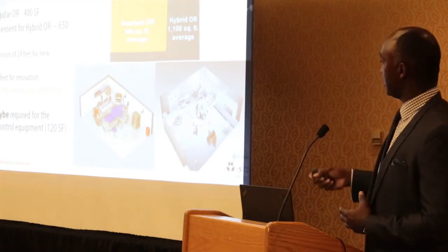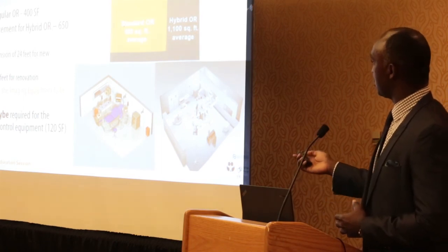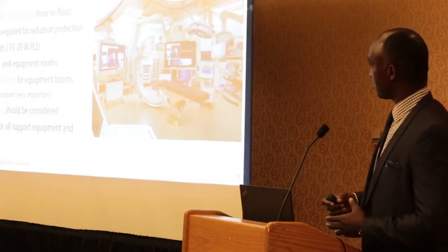A control room is required, which is another 120 square feet. So as designers, as facility managers, whenever you're trying to undertake these projects, there's a huge space requirement. And the minimum size of a hybrid OR that I've seen is 1,100 square feet. So that's the minimum size that you require, so you have to look out and make sure that you're not short on the size of your hybrid OR. And these are just some images of a hybrid OR space.